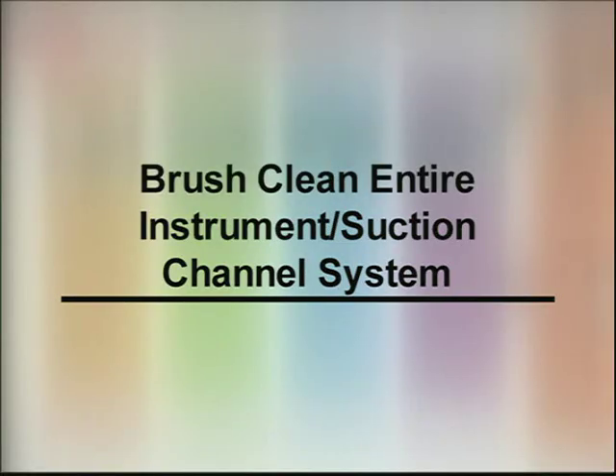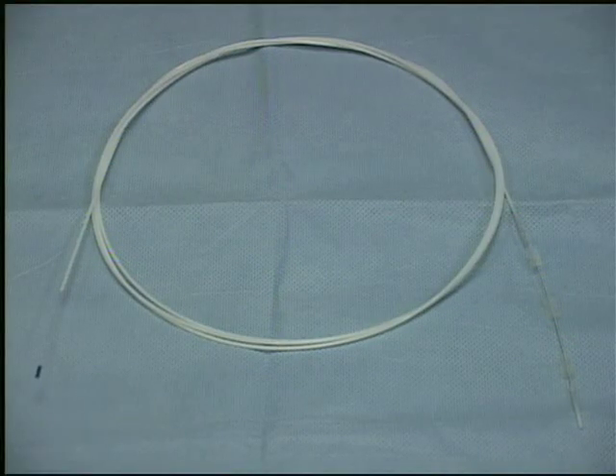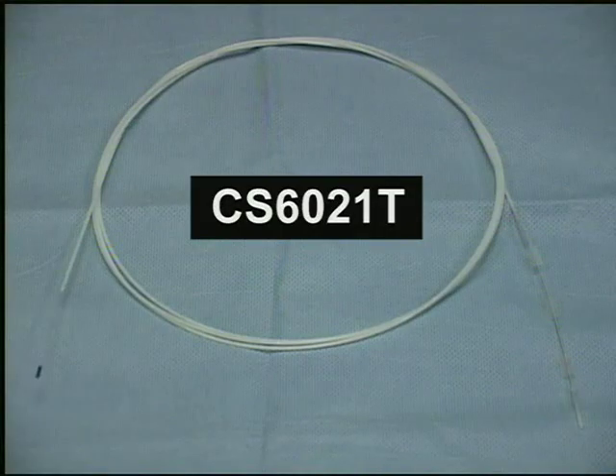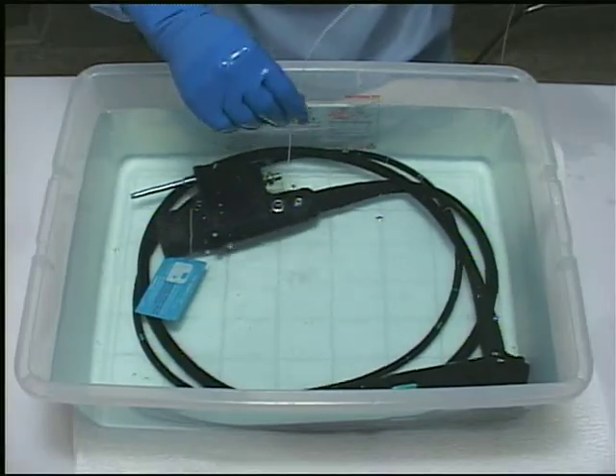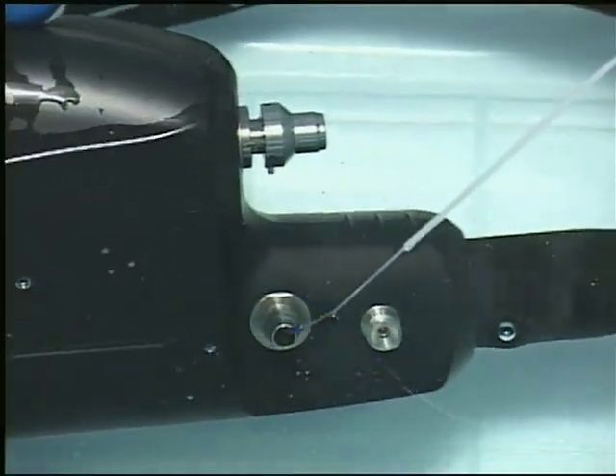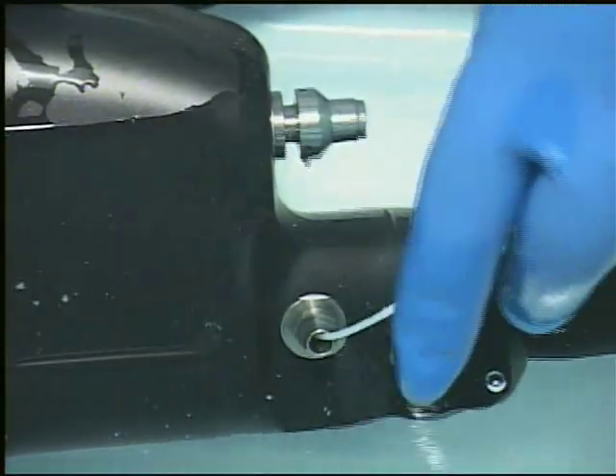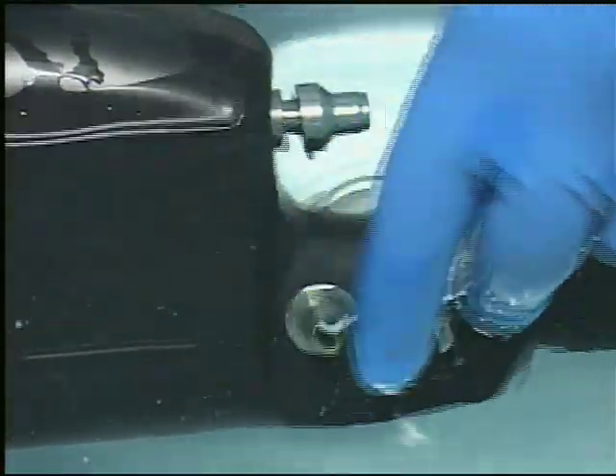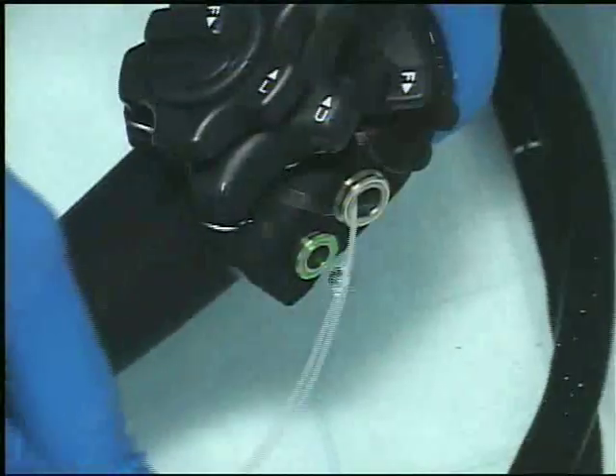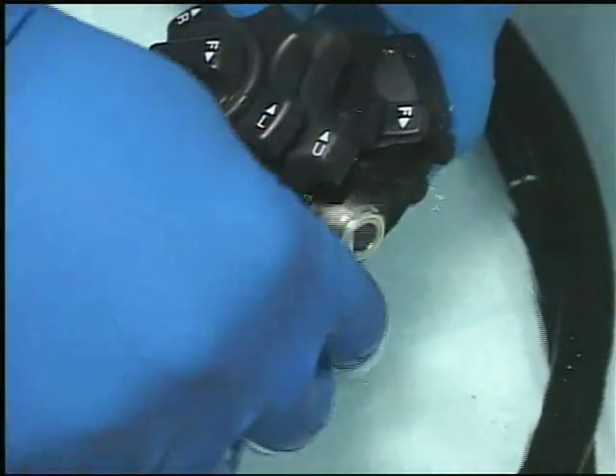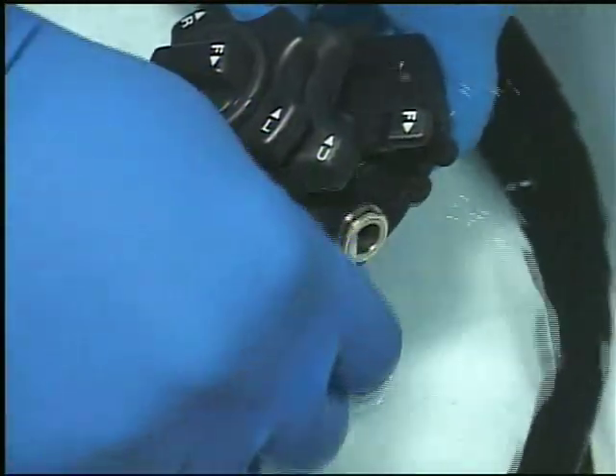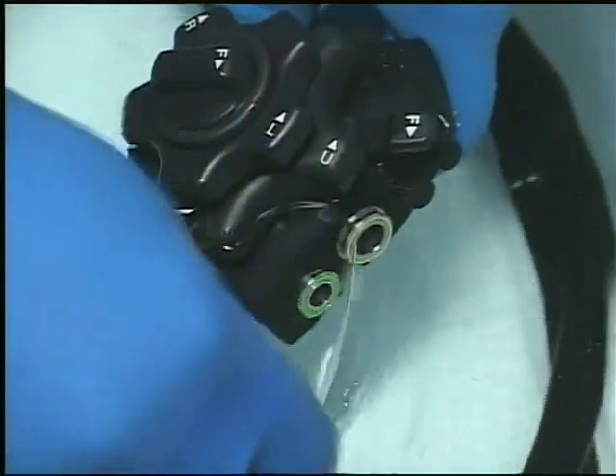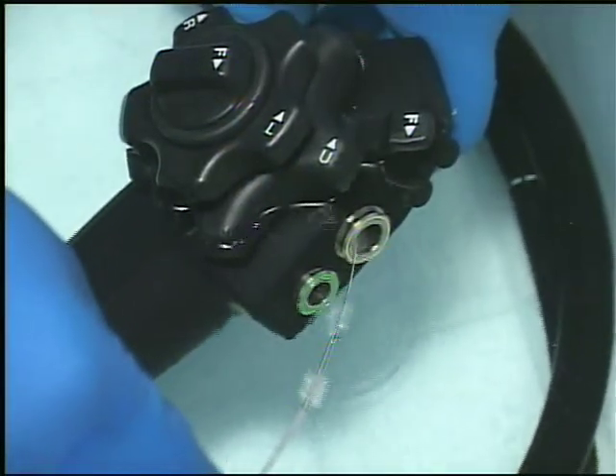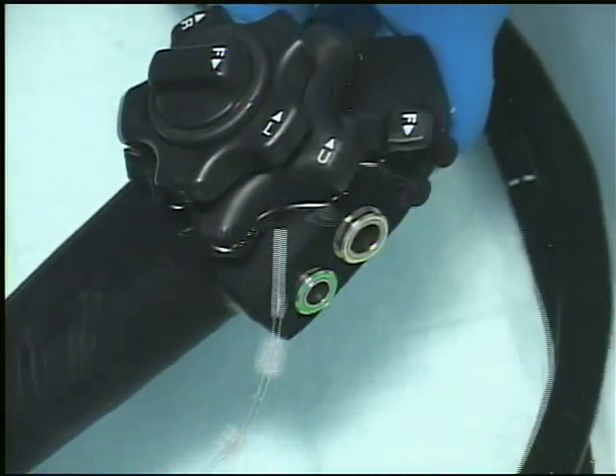Brush clean the entire instrument suction channel system. Using the long single-use cleaning brush CS6021T, insert the back-end blue tip of the shaft of the brush into the opening of the suction nipple and gently pass the brush until it appears in the suction control valve receptacle. Grasp the back end of the brush shaft and gently pull the brush from the receptacle. This will clean the suction tube within the light guide umbilical cable. Repeat if necessary until a clean brush exits the suction channel.